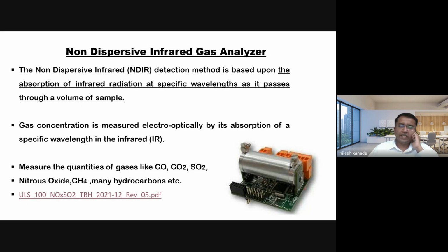Usually the gases are measured in ppm, where 10,000 ppm is equal to 1% volume. So the gases are measured in ppm. If you want to select any sensor, you have to see what kind of ranges it can measure and what kind of gases. In that you can see this sensor can measure up to 5,000 ppm of sulfur dioxide, nitrous oxide, and nitrogen oxides. So here you can see the data sheet.